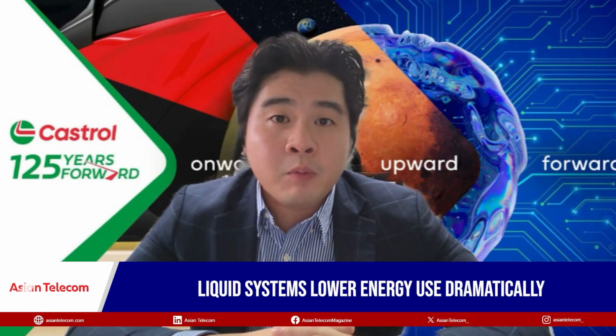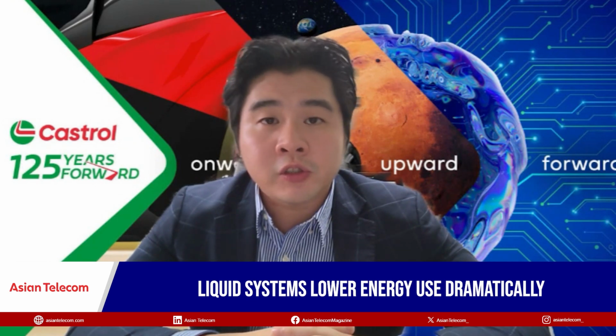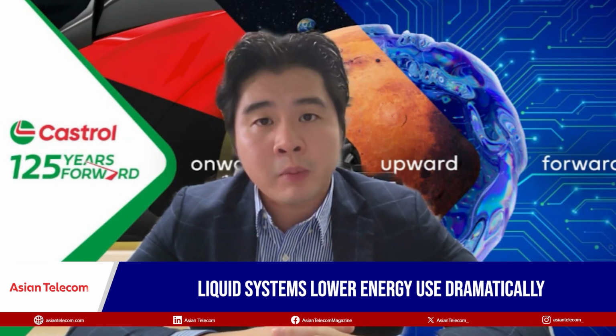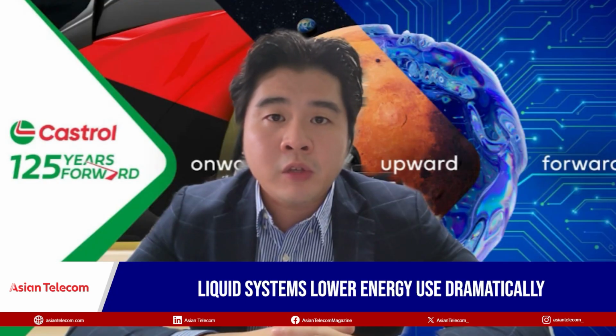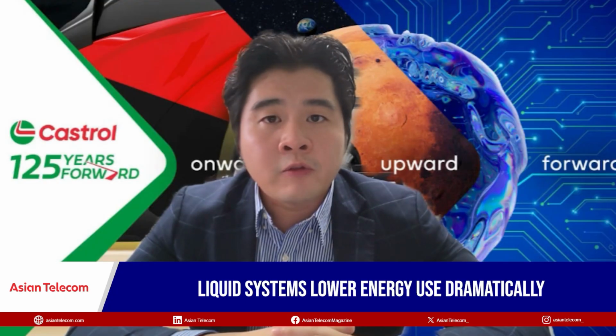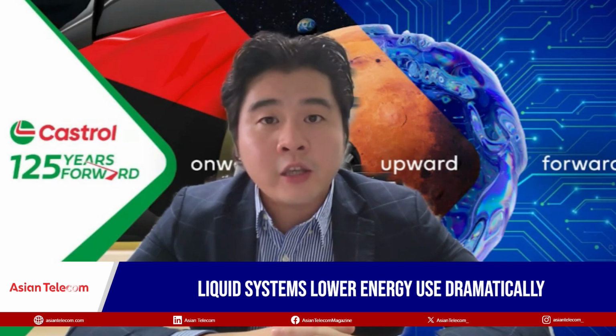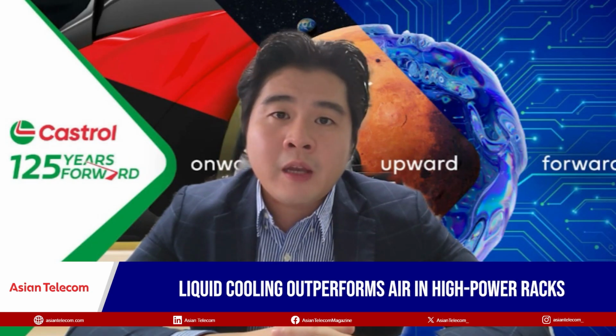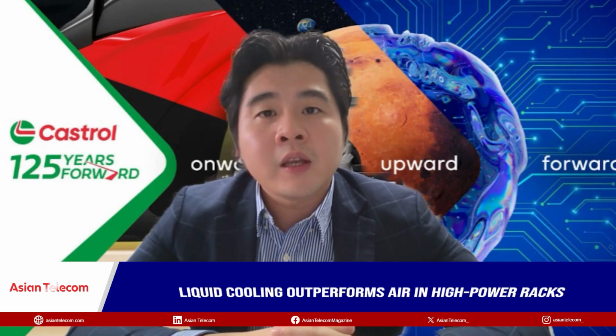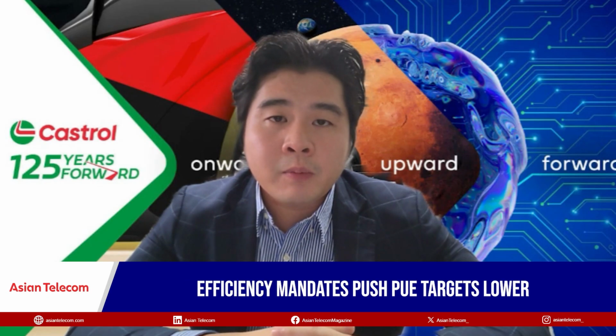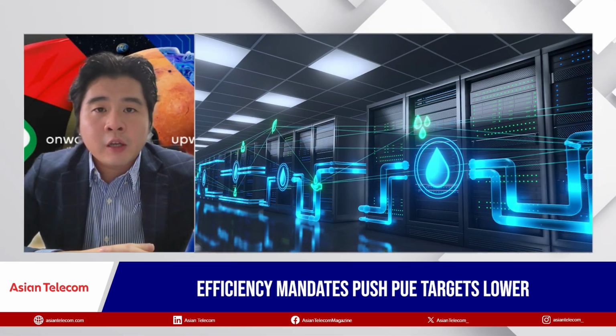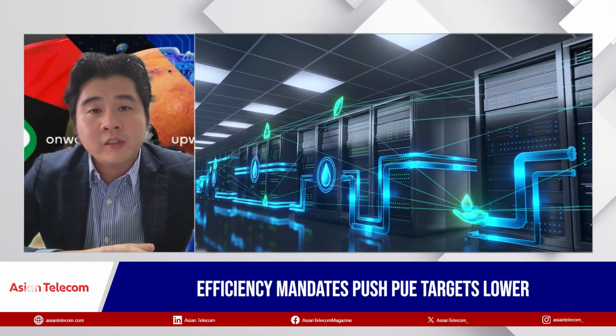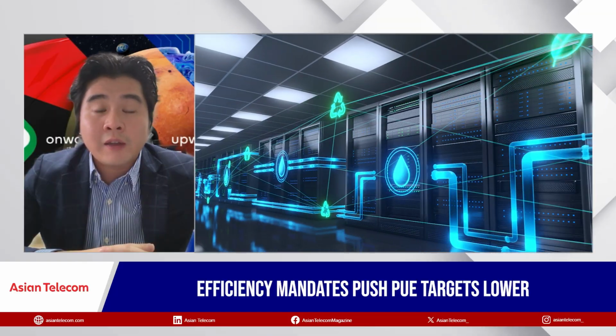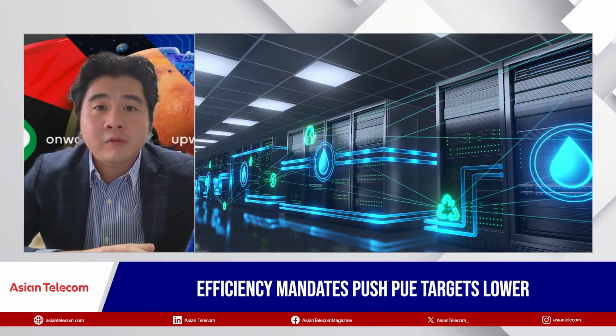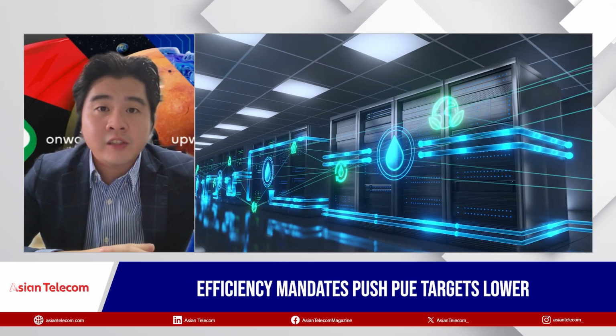It also means the PUE, power usage efficiency, of data center designs across Asia is going to be lower. We see many mandates from different countries requiring it to be lower than 1.2. Lastly, sustainable cost optimization: liquid cooling is proven to have lower total cost of ownership throughout the life cycle of the data center. So it's definitely changing how data center design works.